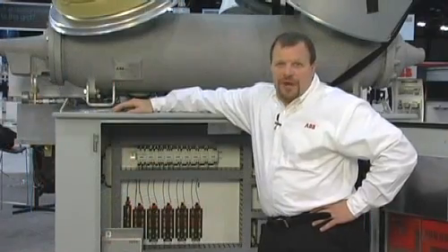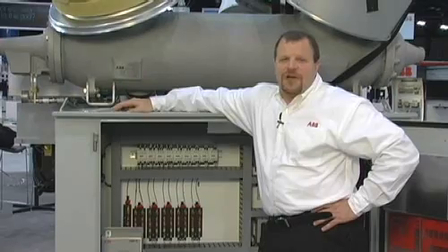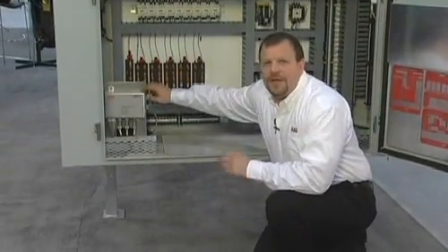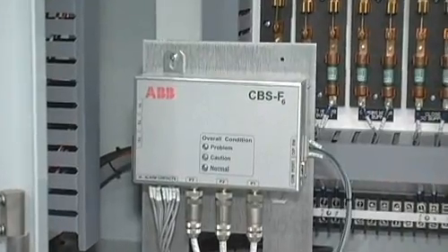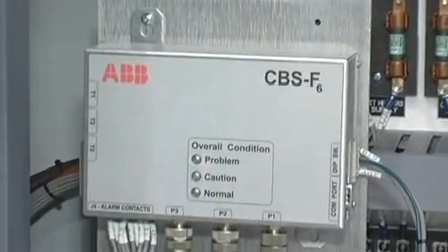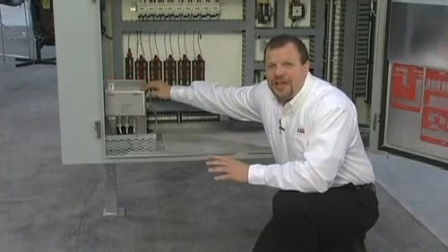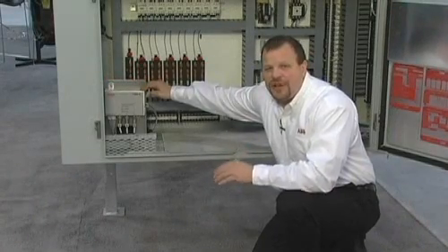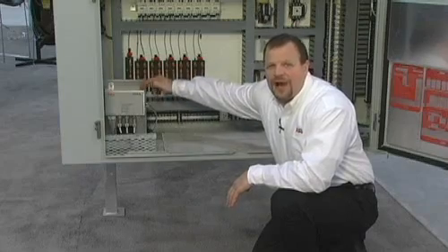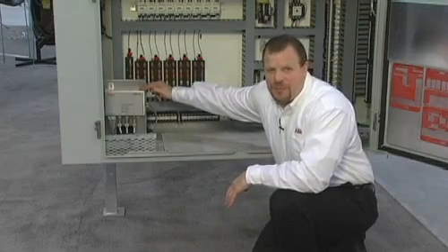My third and final recommendation for managing SF6 gas losses from dead tank breakers is to employ some type of monitoring system. The monitoring system should trend and track the SF6 gas density and temperature over a long period of time, and should also compensate for any changes in climatic conditions and seasonal changes, and give you an accuracy and long-term reliable reading of whether you're actually losing SF6 gas from your system or not.